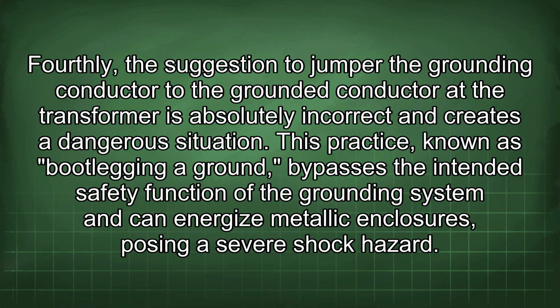Fourthly, the suggestion to jumper the grounding conductor to the grounded conductor at the transformer is absolutely incorrect and creates a dangerous situation. This practice, known as bootlegging a ground, bypasses the intended safety function of the grounding system and can energize metallic enclosures, posing a severe shock hazard.